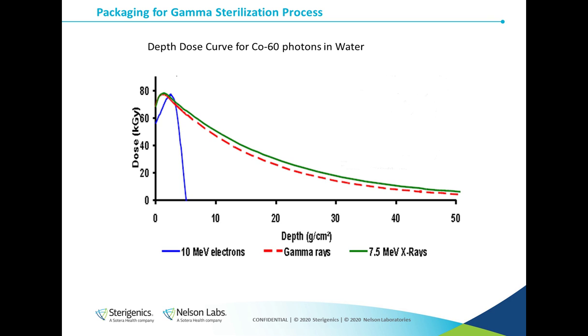This graph shows the depth dose curve for gamma, X-ray, and E-beam irradiation modalities. The dashed red line is the depth dose curve for cobalt-60 gamma photons. On the x-axis, we have used the unit of grams per square centimeter, or what we would refer to as areal density. If you were to assume that the material we are irradiating is water with a density of 1 gram per cubic centimeter, then the x-axis can simply be viewed as centimeters. So for cobalt-60 photons, you can see that the maximum dose is at or near the surface of the material or package that we are irradiating, and then drops off to about 50% of the surface value at between 10 and 12 centimeters of water.